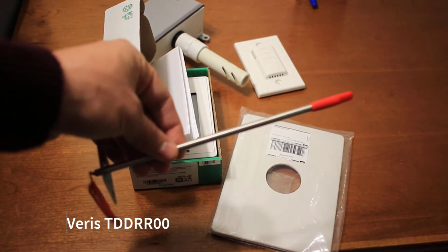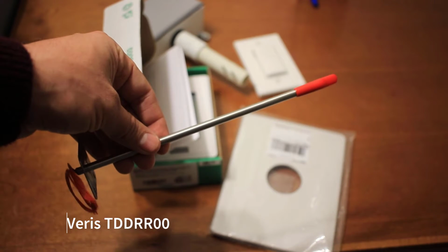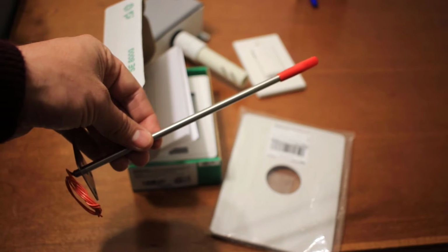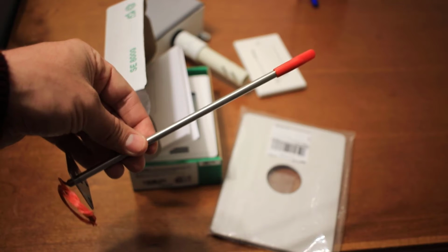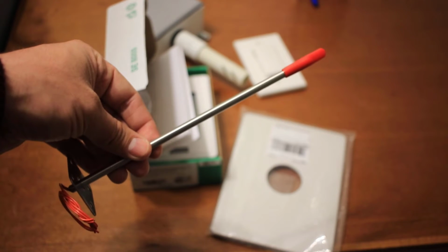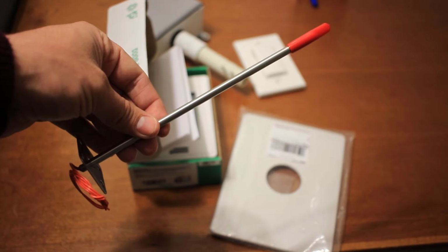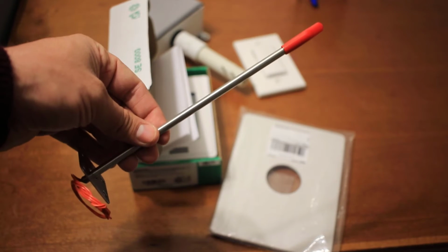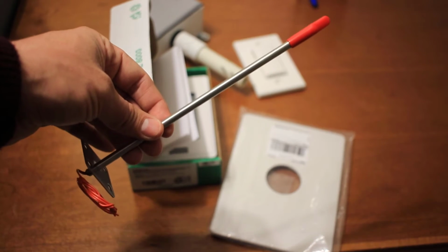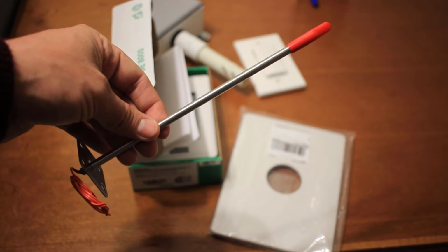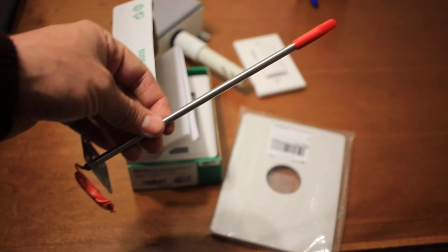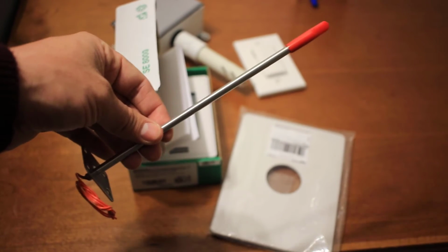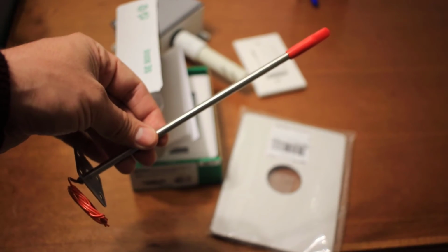Next piece that we're going to see here is our discharge air sensor. We can put this up in a duct, and we can be grabbing the discharge air. We always recommend that you put a discharge air sensor on a system. It really helps validate whether your system is working correctly and helps troubleshoot any units that you have in the future. For instance, if you have a call for cooling, we see that the SE8650 is calling for cooling, both compressors are on, but our discharge is sitting somewhere up at around 75, 80 degrees. We know that there's a problem with our units, that those compressors aren't kicking on. So a very, very useful sensor to include in your Building Insights option.